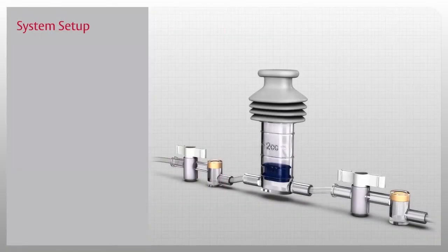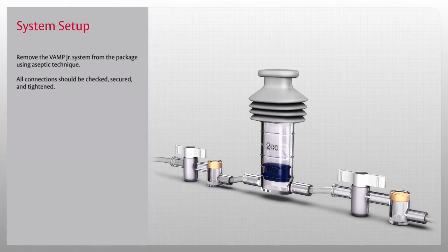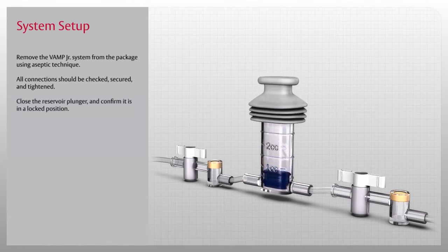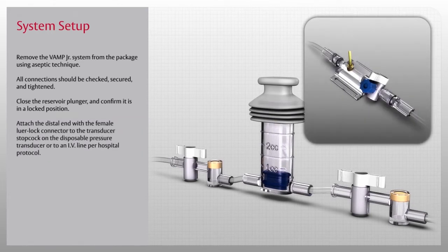Now that you've been introduced to the VAMP Junior system, let's start our in-service by setting it up. To begin, remove the VAMP Junior system from the package using aseptic technique. All connections should be checked, secured, and tightened. Close the reservoir plunger and confirm it is in a locked position. Now, attach the distal end with a female luer lock connector to the transducer stopcock on the disposable pressure transducer or to an IV line per hospital protocol.